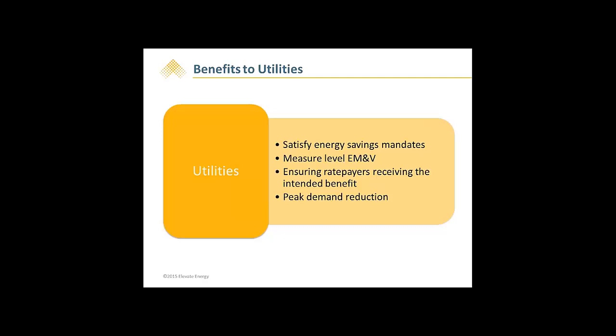Second, evaluation, measurement, and verification, or EM&V. Verified savings is gaining steam in the energy efficiency business. I've even heard that sometime in the near future, verified savings will be required by statute. Because HVAC performance is measured and not deemed, it inherently introduces EM&V into a program where it's otherwise not currently offered. Third, many utilities are motivated simply to ensure their ratepayers are getting the full benefit of the efficiency investment they're paying into. HVAC performance creates a clear line of accountability for the contractor that protects the customer ratepayer.